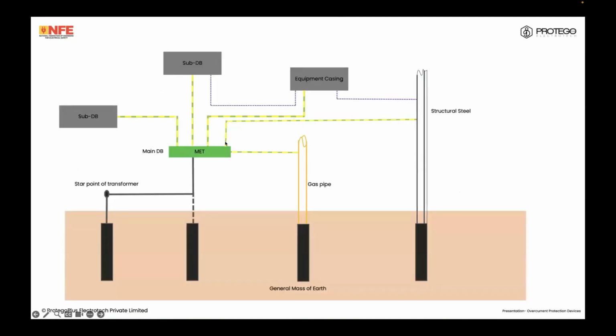This is just an image to show you that we connect to the MET all the individual class 1 equipment, the DBs, equipment casing. There may be protective supplementary equipotential bonding, and we obviously bond the gas pipe and structures, which are extraneous conductive parts, to the MET, which is then connected to your star point of the transformer. You may also have an electrode on site.